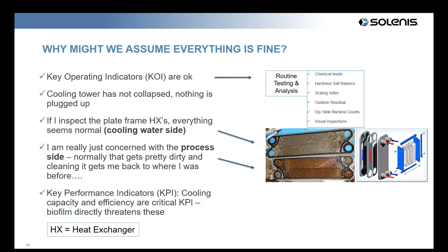So the key performance indicator on the cooling tower is really what we need to be looking at, not the key operating indicator, and that's really what you're trying to monitor. How much heat am I actually transferring, and how much corrosion do I actually have? And those can be monitored quite a bit differently.